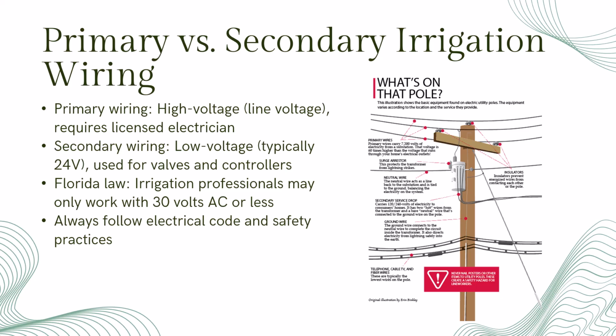What we can work on is the secondary wiring, which is typically 24 volts AC. This is what controls your valves and most decoder-based systems. Florida law makes it clear we can only legally work on circuits that are 30 volts AC or less. So when you're planning your wire routing or troubleshooting, it's essential to know which side of the system you're working on and when to call in an electrician.